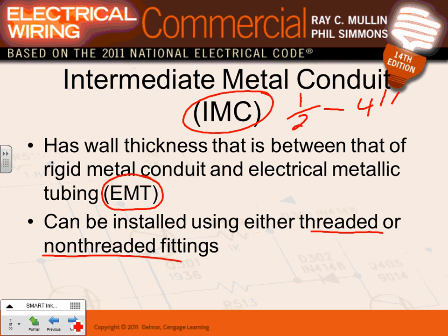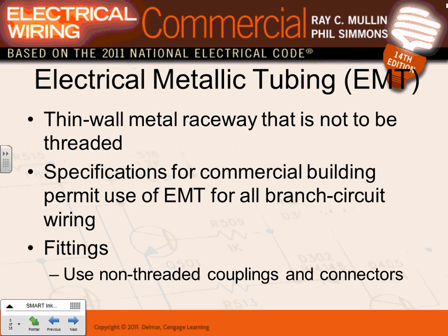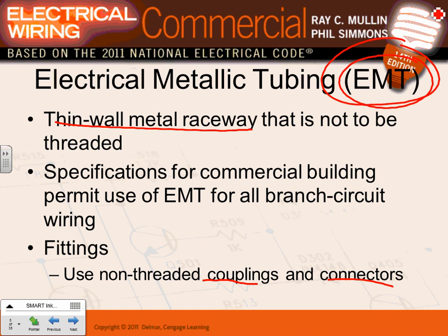Moving on to your conduit of choice - please highlight this one. These are non-threaded EMT conduits. It's a thin-wall raceway, non-threaded. In our project it's specified for branch circuits and feeders. Fittings use non-threaded couplings and connectors. The conduit of choice, unless you have severe physical protection requirements, is going to be EMT.